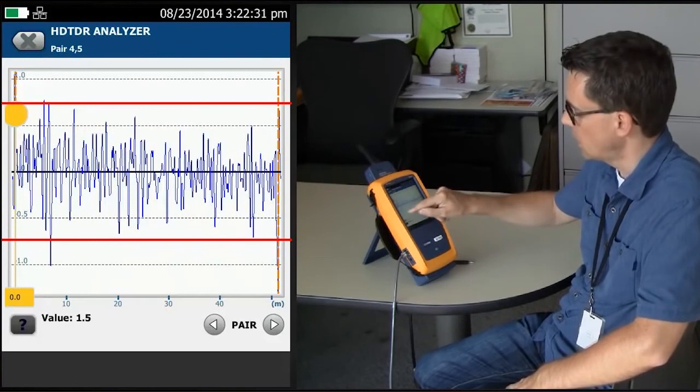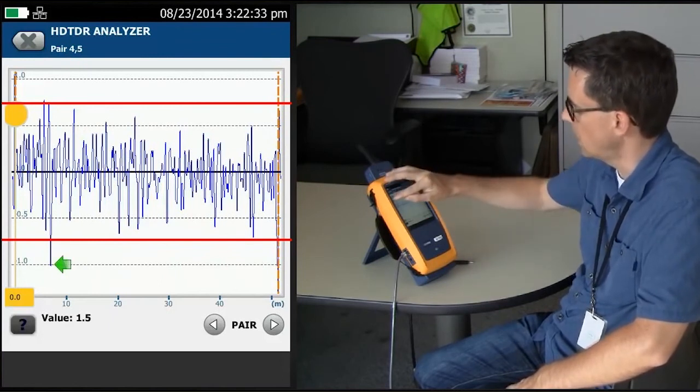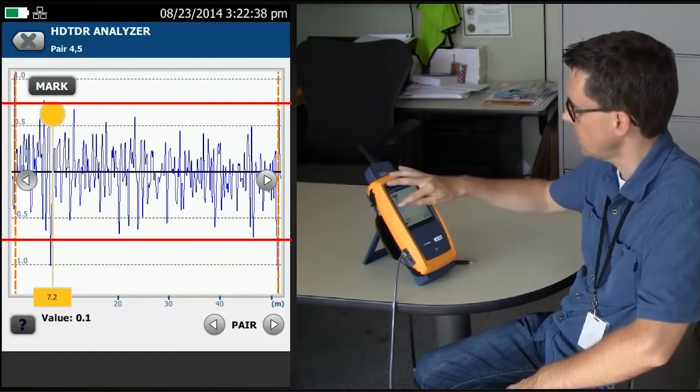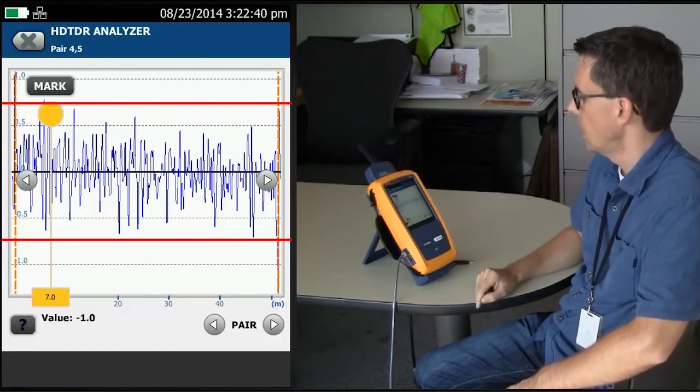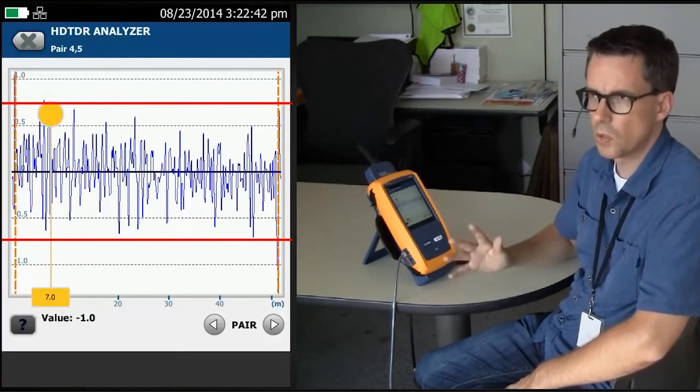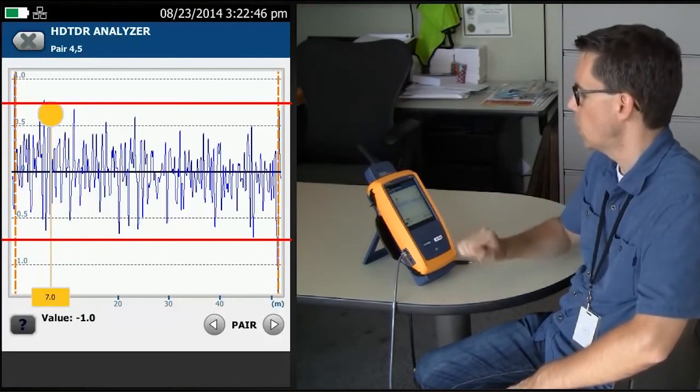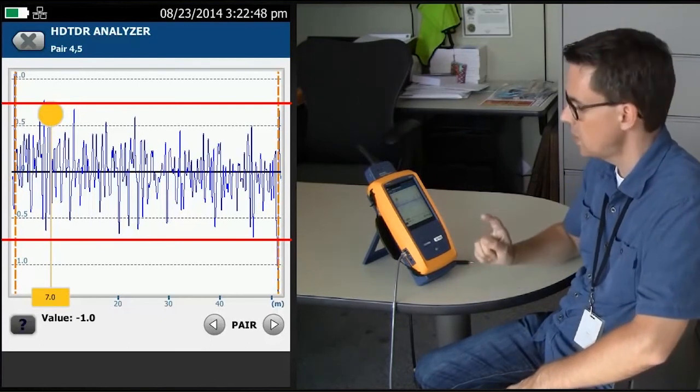Of course, somebody might spot this here, this little spike here, and indeed, I can move my cursor to that location. Let me fine tune that, and around about 7 meters, 23, 24 feet, it's found an anomaly that exceeds our 0.8. Now, this is very important.